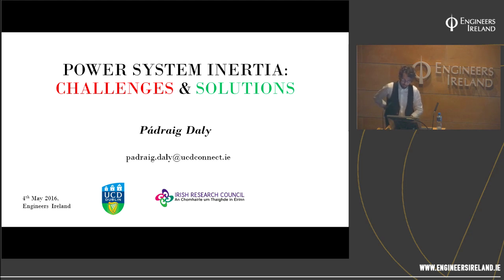What I'm guessing they were getting at, and I don't want in any way to speak for the system operator, but I don't want to bash them, because I'm pretty sure, this is all me saying this now, if it is the RoCoF Alternatives report. And as I've said in my presentation, emulated inertial controls is not the same stuff as synchronous inertial response. And it's the synchronous inertial response. If you extend that RoCoF measurement time window, then power electronic controls can come in at the end to improve it. But currently, it's synchronous inertial response that you want to improve your rate of change of frequency.